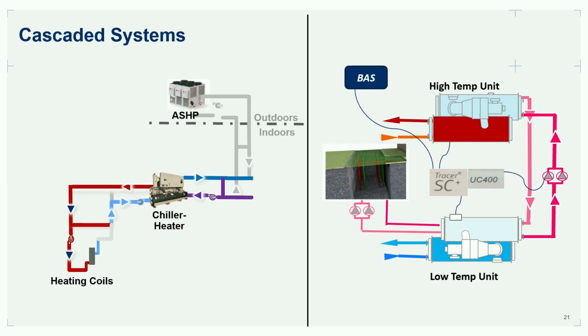On the geothermal side, similar concept. Well-field, let's say we're getting 45 degree water in to the evaporator on a low temp unit, which, by the way, is every chiller you have in your buildings today. There's no difference in a low temp unit. We've got a lot of existing infrastructure. Let's not just throw it out, let's use it to our advantage. So we're going to have that 45 degree water in, another standard set of lift, get 110 out maybe. Put that into the evaporator on the high temp side, which could be another centrifugal chiller or another screw chiller, and then do another standard set of lift.